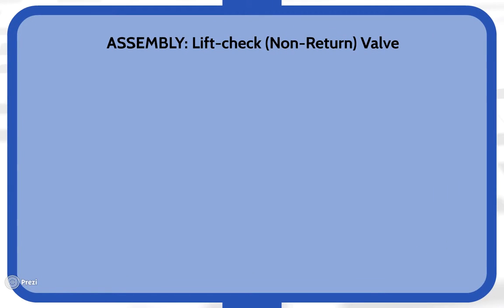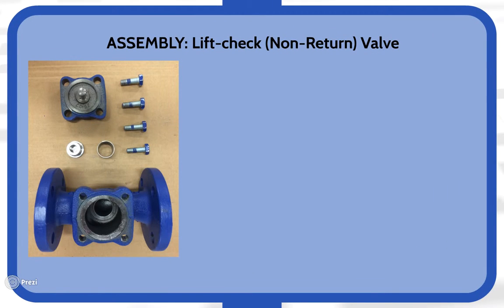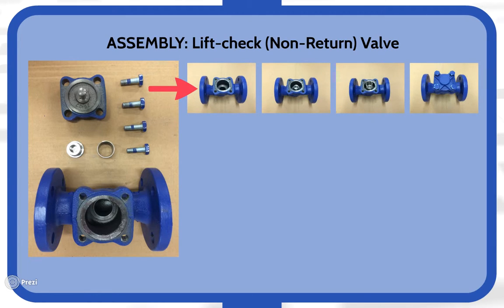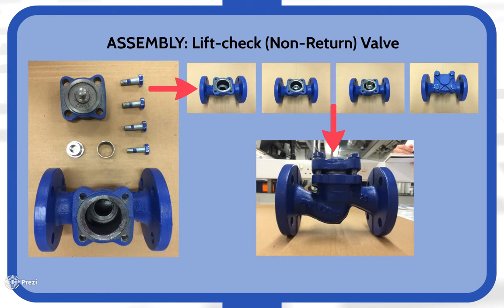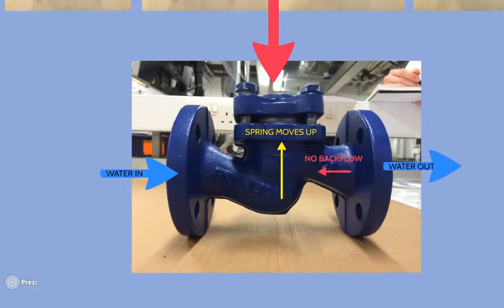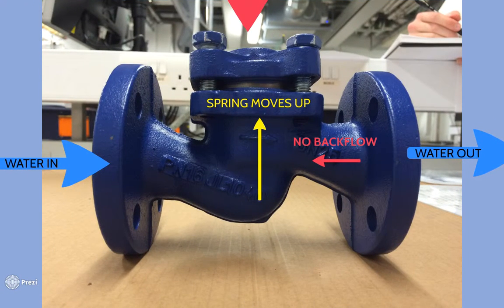The lift check, or non-return valve, operates on a spring basis and the use of the pressure exerted by the water. The valve is assembled by firstly adding the spring and a circular piece into the bottom half of the valve, then adding the top half and screwing it in. As we can see, the water enters through here and when with enough pressure it will force the spring upwards, allowing the water to flow in the forward direction. The water cannot flow in the other direction as the spring part would block off the passage.